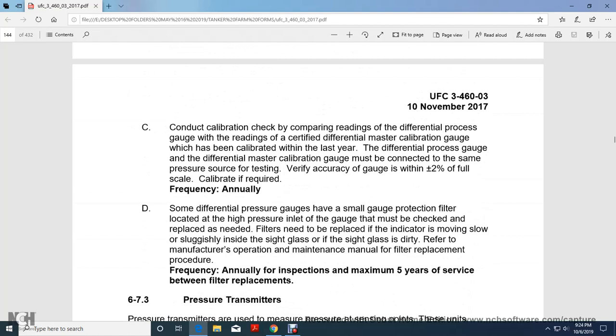Conduct a calibration check by comparing the reading of the differential pressure gauge with the reading of a certified differential master calibration gauge, which must have been calibrated within the last year. The differential master calibration gauge must be connected to the same pressure source for the testing, to verify the accuracy of the gauge within plus or minus 2% of full scale. Calibrate if required, annually.